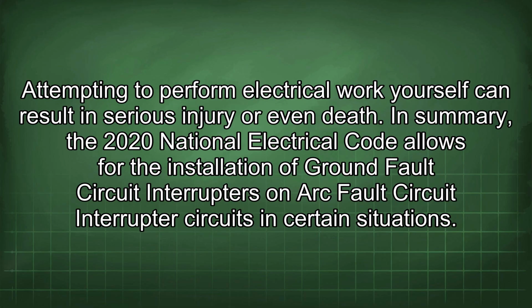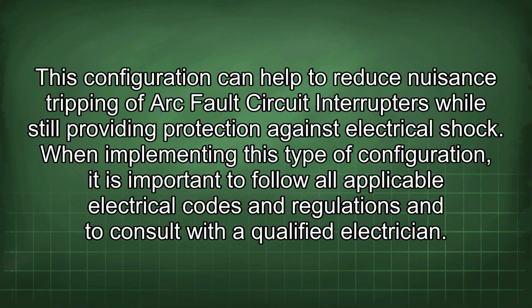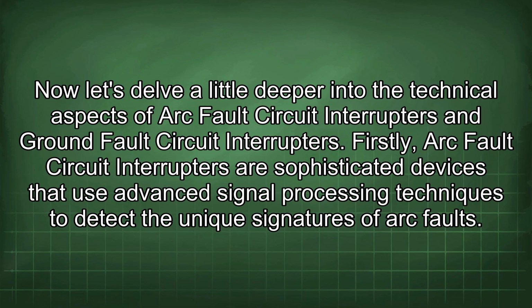In summary, the 2020 National Electrical Code allows for the installation of ground fault circuit interrupters on arc fault circuit interrupter circuits in certain situations. This configuration can help to reduce nuisance tripping of arc fault circuit interrupters while still providing protection against electrical shock. When implementing this type of configuration, it is important to follow all applicable electrical codes and regulations and to consult with a qualified electrician.